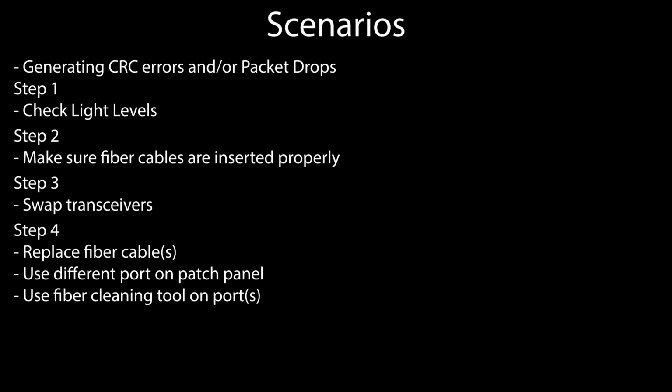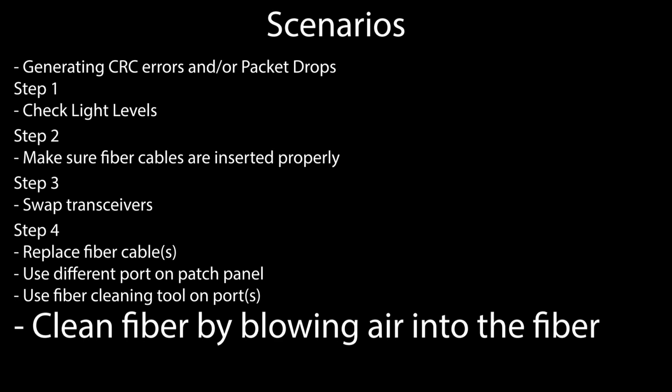The old school way of doing this was to actually blow air from a distance on the fiber to remove the dust and debris out of the fiber core. Shockingly, I actually did this on my own. I actually gained 1 to 2 dBm from -7 to -5 after this technique.